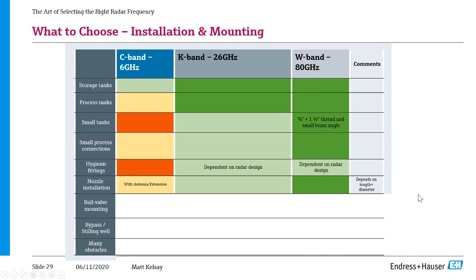For nozzle installation, your higher frequency is going to be better suited for this. So we can measure through tall, narrow nozzles without the need for any antenna extension. In the past, before high frequency radar, we could measure through tall nozzles, but we had to use what's called an antenna extension. More or less it puts a rod between the process connection and that horn style antenna, and it just extends it down into the tank, as it's ideal to have that horn extending just down into the vessel itself. So it was possible, but it led to additional cost to manufacture. And now you've got this really big antenna extension on the end of a radar that's difficult to mount.